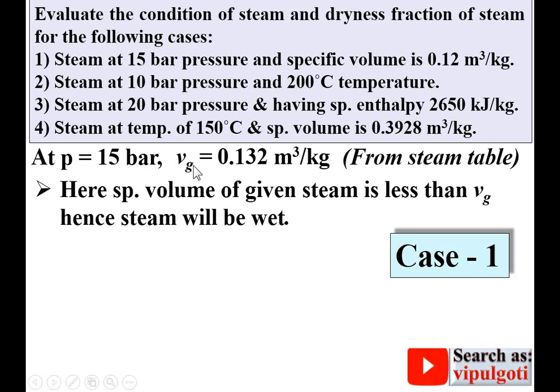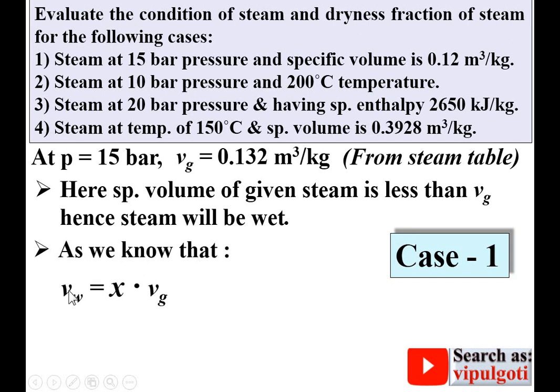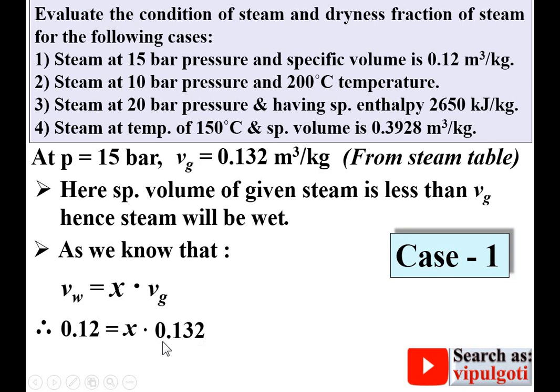Since the given specific volume of 0.12 m³/kg is less than Vg of 0.132 m³/kg, the steam is wet steam — it is not dry saturated steam. Now to find the dryness fraction, we use: specific volume of wet steam = x × Vg. So 0.12 = x × 0.132, giving dryness fraction x = 0.91.